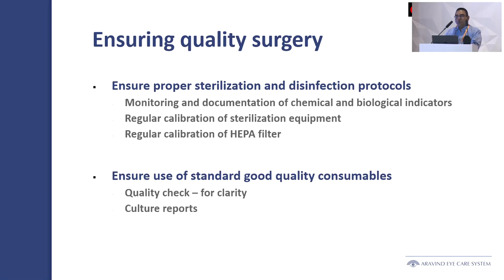Ensuring quality surgery starts with ensuring proper sterilization and disinfection protocols. So there should be monitoring and documentation of all the chemical and biological indicators. Regular calibration of the sterilization equipment which we are using, be it autoclave or ETO, and regular calibration of the HEPA filter and other environmental factors. Again, ensure use of standard good quality consumables, always from reliable vendors, not changing the brand often, but staying true to a brand which has given good results.